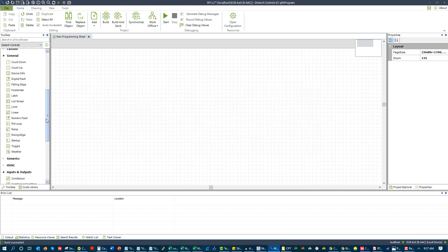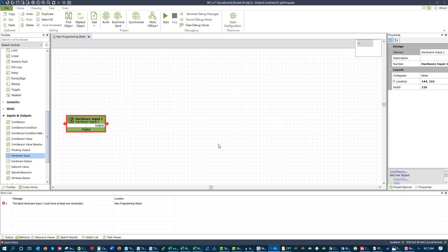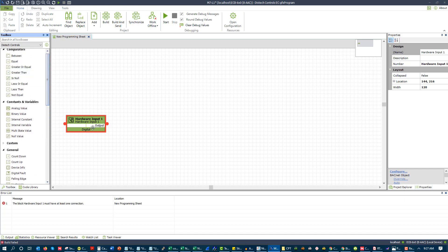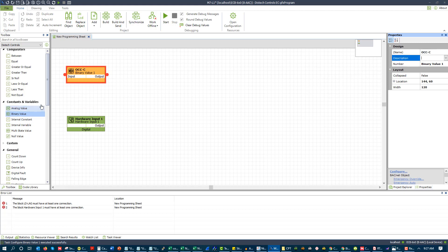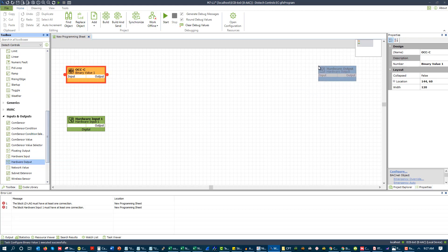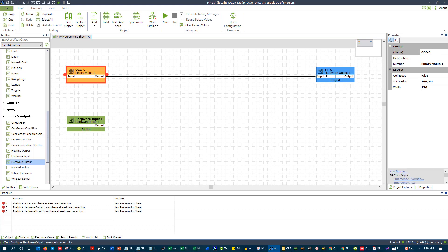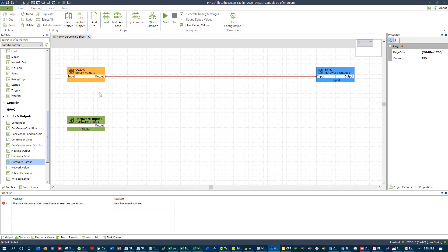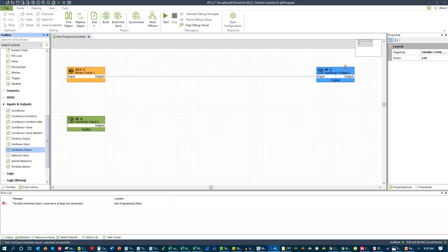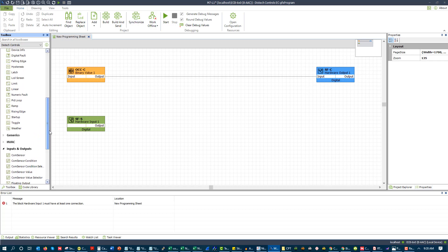Now let's take another pattern. Let's say we were told: when a supply fan is commanded on — the supply fan is commanded on based on occupancy — and then the supply fan will stay on unless it has a run failure or a status failure. And if it has either of those after 30 seconds, it's going to latch on to require manual reset. So we're going to have our occupancy command to our hardware output to our supply fan command. This is an occupancy command pattern right there — pretty straightforward. We're going to have our supply fan status.